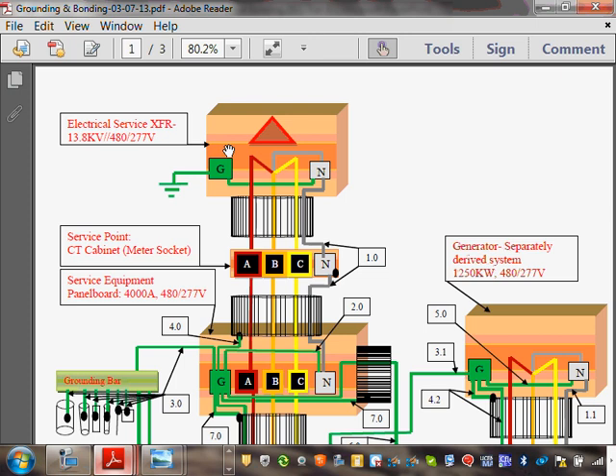By the way, if this was an ungrounded system, everything that you see in this sheet stays identical. The only thing that's different is you see that number 1, the gray neutral coming in, that will disappear. And of course with the neutral comes the main bonding jumper that ties the neutral to the ground. This will disappear. Your neutral will disappear in an ungrounded system. Everything else stays the same if your system is ungrounded. If your system is impedance grounded, the same thing.